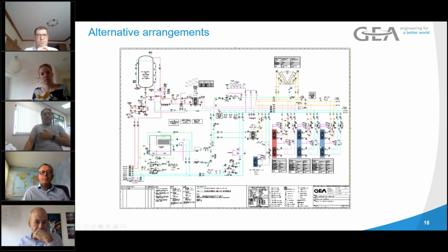This is another way of doing it. These ones are for food process factories, where they produce ready meals, pasta, and that sort of thing. Again, we're doing cooling with some cooling chillers, and we're doing heating with heating chillers. But in effect, the heating chiller, which is cunningly coloured red, is in parallel with the heat rejector. So when we have a heat requirement, which is the buffer tank on the left-hand side, we just boost it up, and in this case it's 70 degrees, and then it only rejects the excess heat from the refrigeration process.